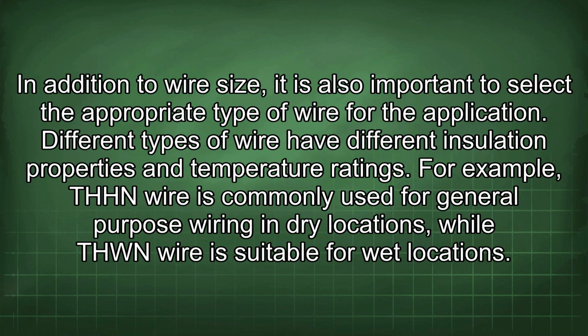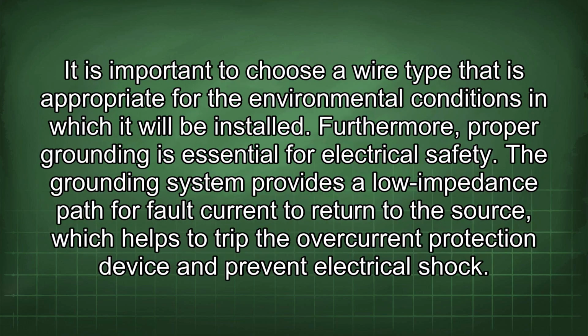In addition to wire size, it is also important to select the appropriate type of wire for the application. Different types of wire have different insulation properties and temperature ratings. For example, THHN wire is commonly used for general-purpose wiring in dry locations, while THWN wire is suitable for wet locations. It is important to choose a wire type that is appropriate for the environmental conditions in which it will be installed.